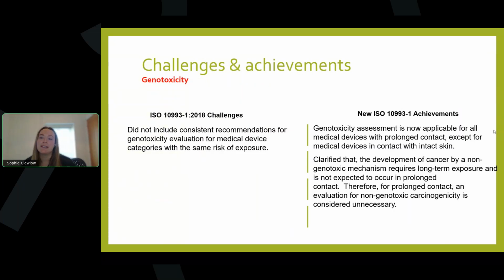Thank you. So the final change that I'll touch on is the implementation of a more consistent approach to genotoxicity evaluations. With the new 10993-1, genotoxicity evaluation is now applicable for all medical devices with prolonged contact, except for medical devices that are in contact with intact skin. In the previous version of the standard, genotoxicity evaluations were not indicated for devices in prolonged contact with mucosal membrane or breached or compromised surfaces, but were indicated for prolonged contact with other tissue types. So genotoxicity evaluations are now more consistent according to contact duration.